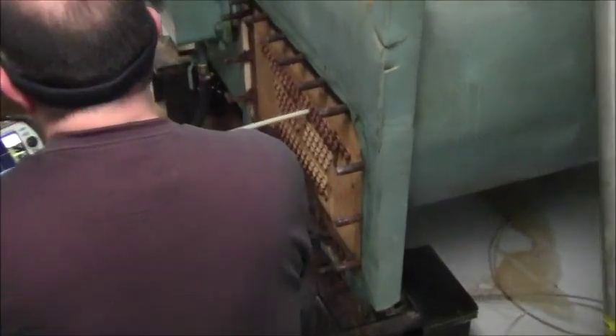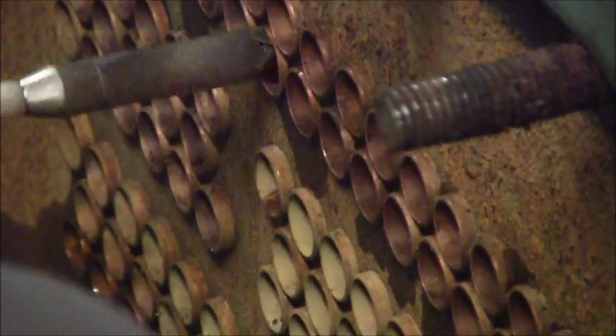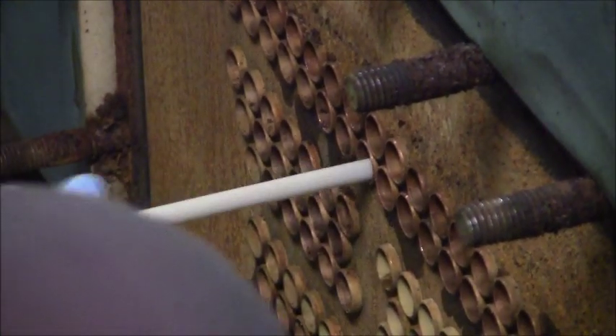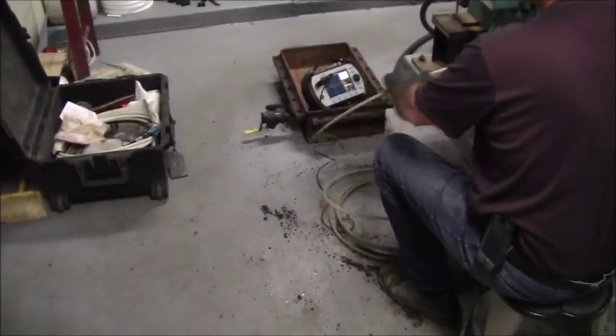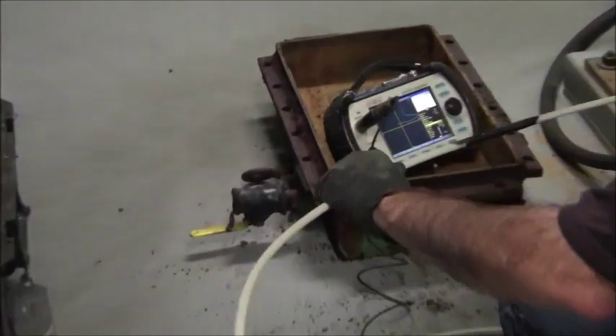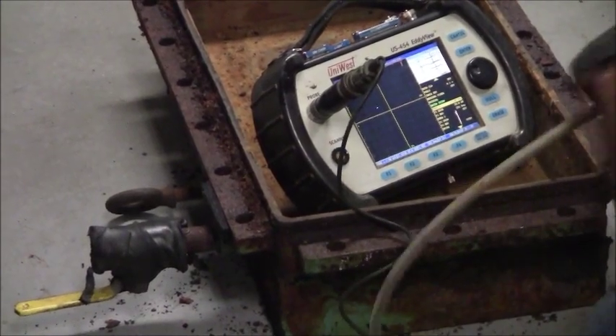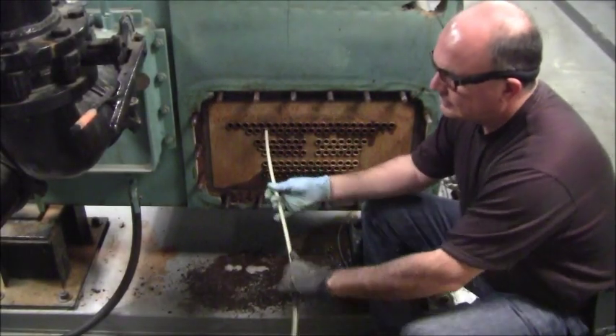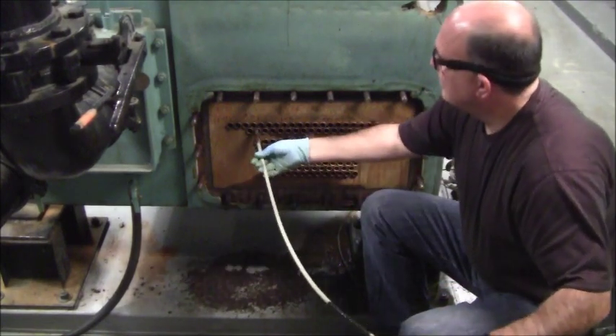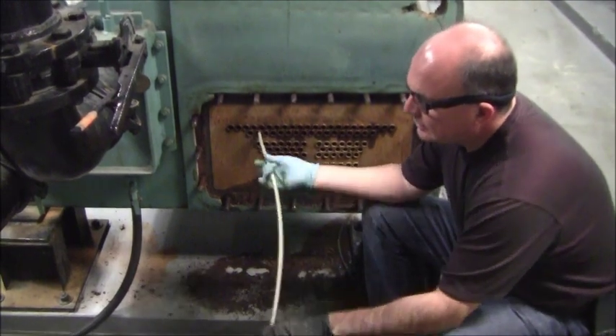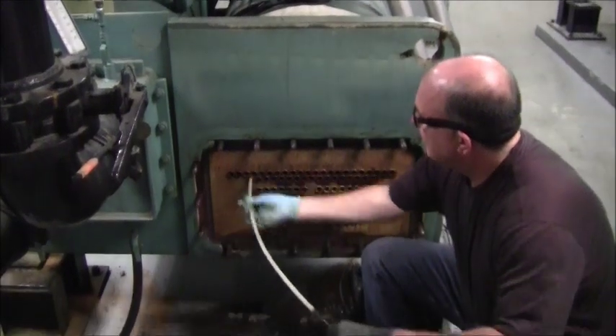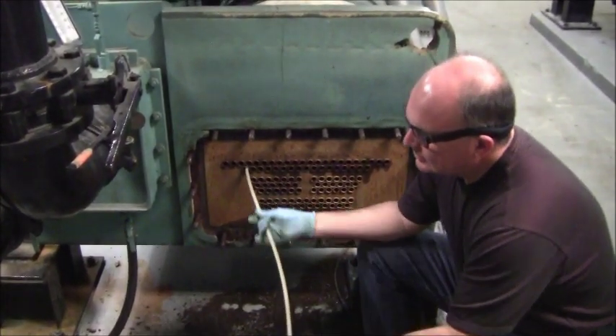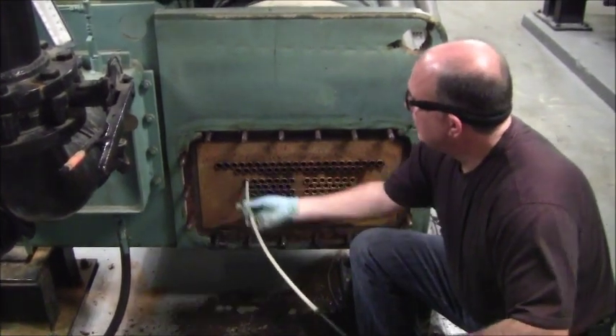You'll see right there how he's doing that. And then that's the sensor head that you see at the very end. But it's a pretty fast process once he gets his machine set up. And he is at that point running the eddy-current test. So this is the evaporator section that he's on now. You can tell that it's the evaporator section because of the insulation surrounding the shell and tubes. The condensing section doesn't have that insulation. The flat section there is the tube sheet, and then he's going in through the tubes.